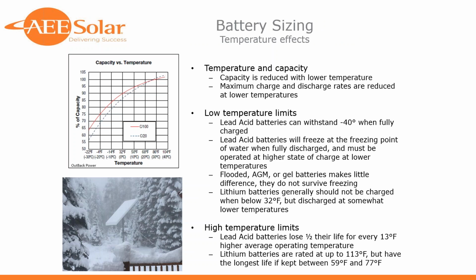We get a lot of questions on temperature and how that plays into battery selection and battery sizing, right? Right. Yes, it is definitely a consideration. Batteries are a chemical reactor, and they like to run at a certain temperature. And the manufacturers have to optimize all this chemistry and the construction of the battery for a certain temperature. And of course, the most common temperature is room temperature, and so that's generally where they're optimized. You can get batteries that are optimized for higher temperature or lower temperature, but they're fairly uncommon, and of course have other issues if you do that.